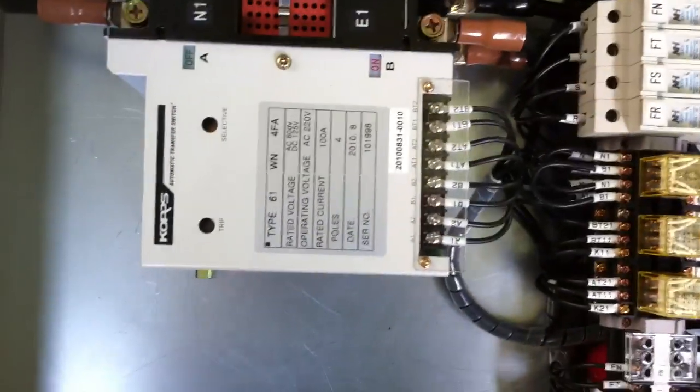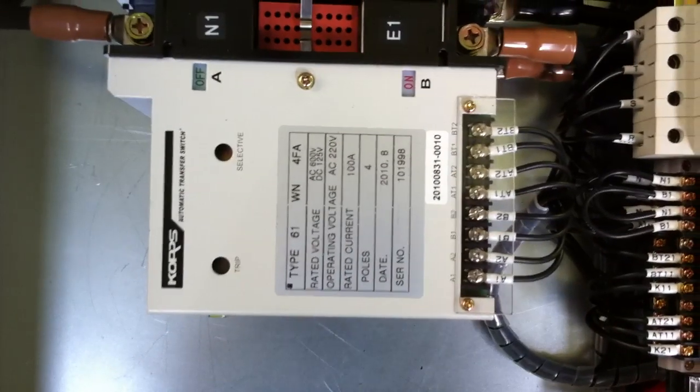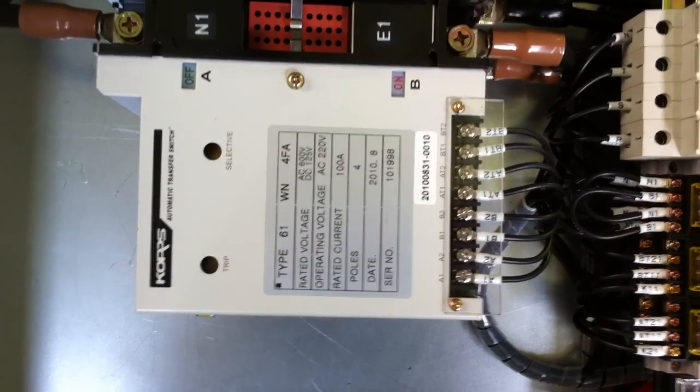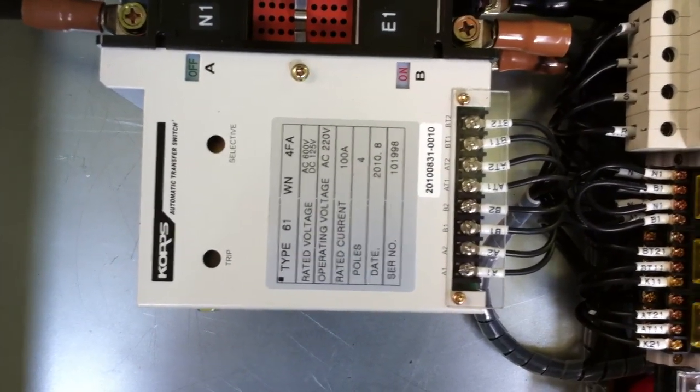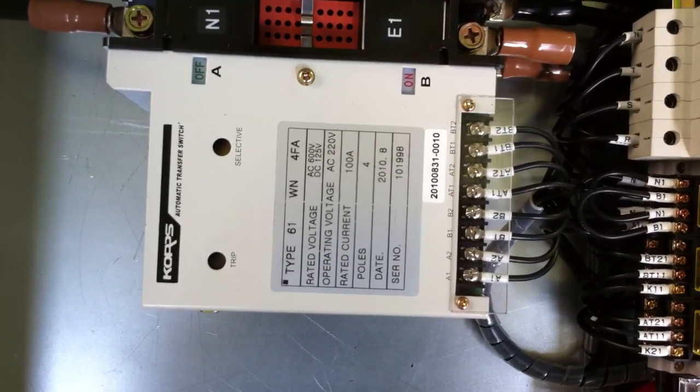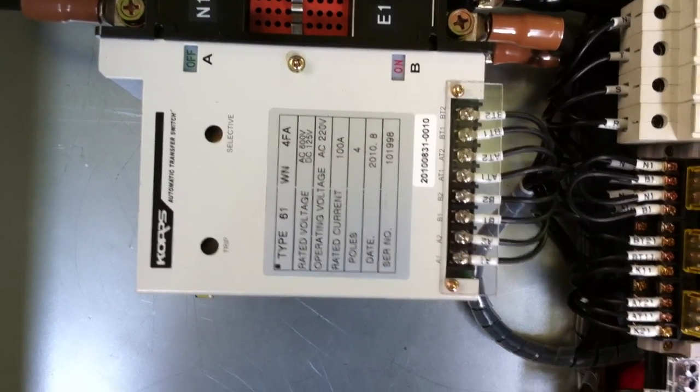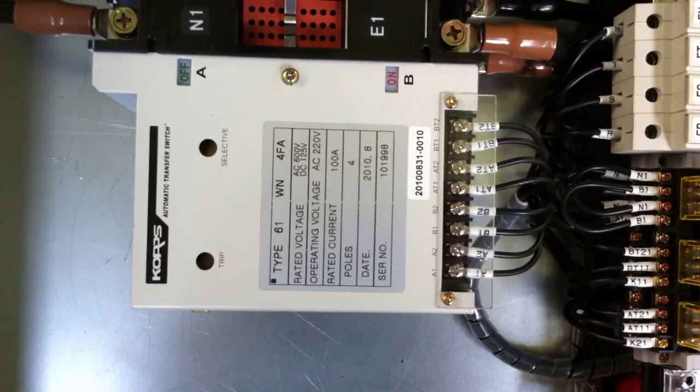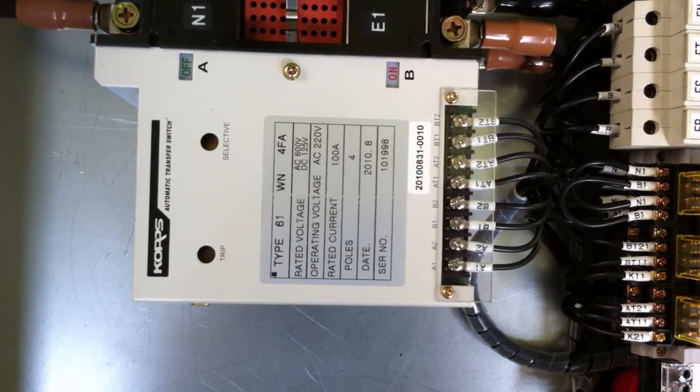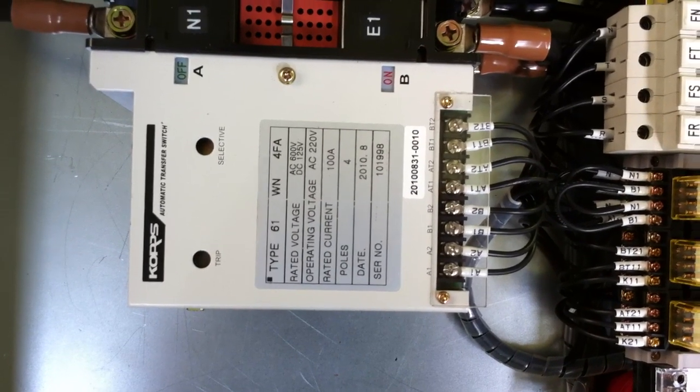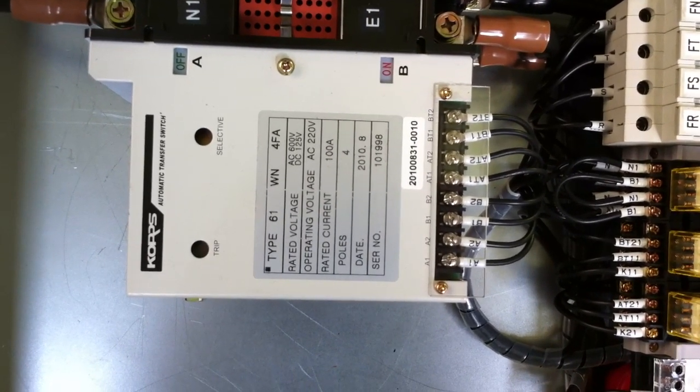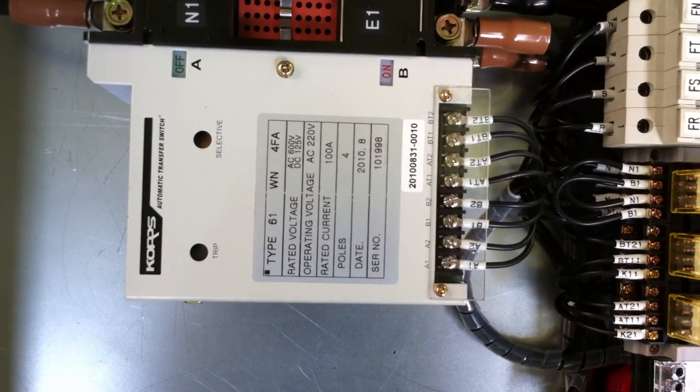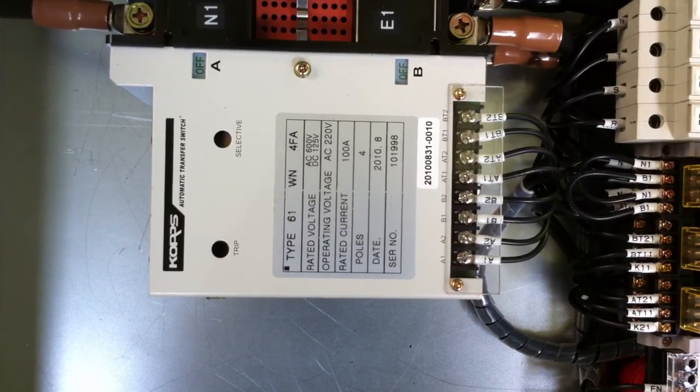So coming back to the ATS panel, we've got generator B on and then mains A off. What will happen is the B switch will go off and then A will come on to return back to mains power.